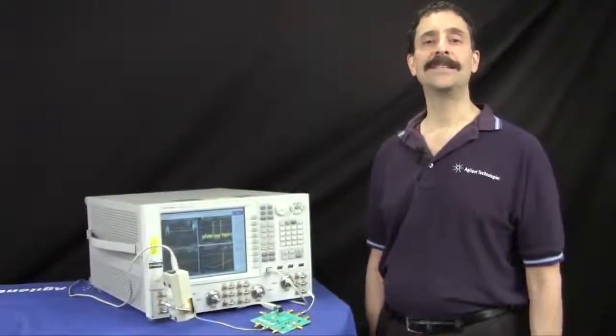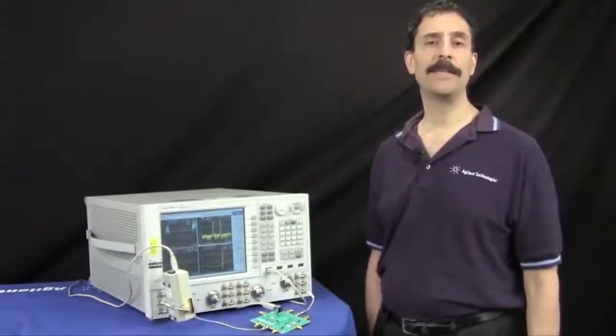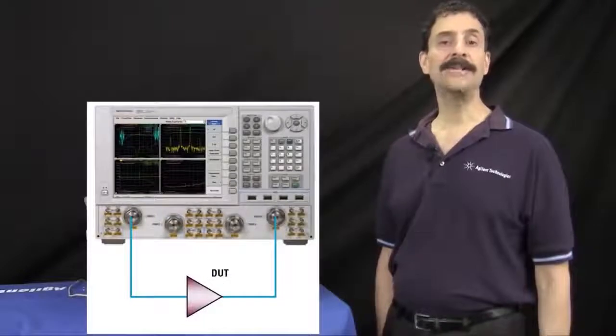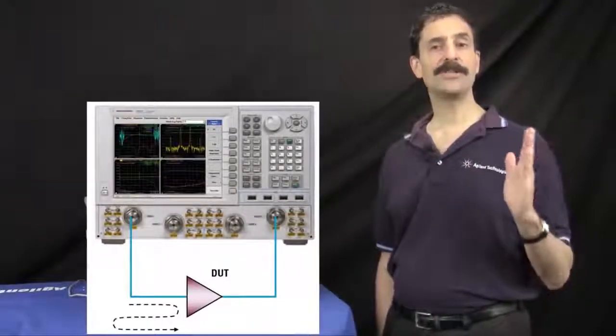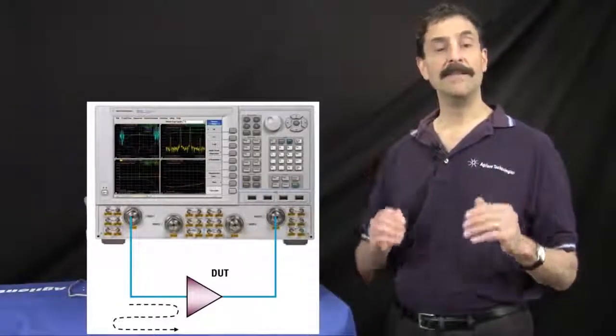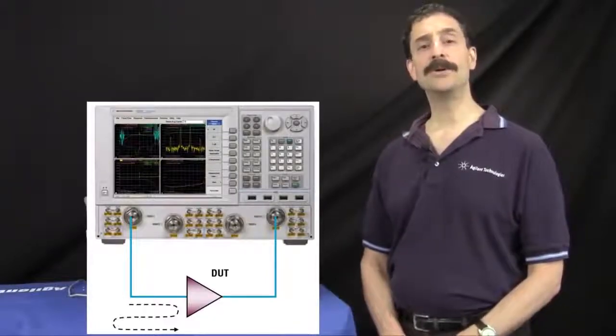Part of the PNA-X's high accuracy comes from using vector error-corrected S-parameters to measure the available gain of the DUT. This standard technique corrects for mismatch between the imperfect source match of the test system and the input impedance of the DUT. Mismatch correction is also applied when measuring the DUT's output noise power.